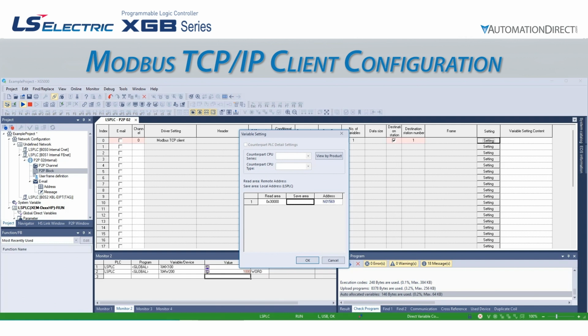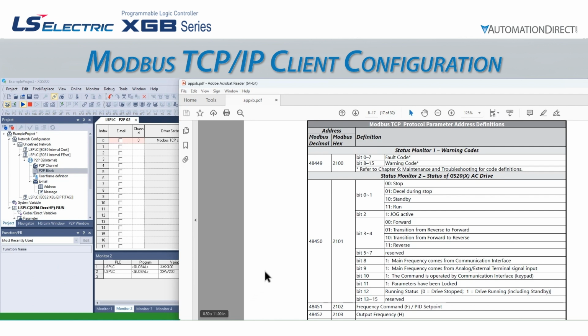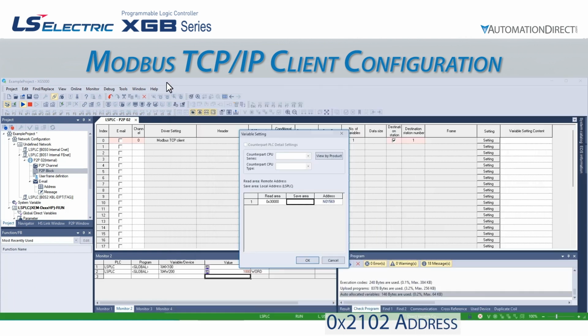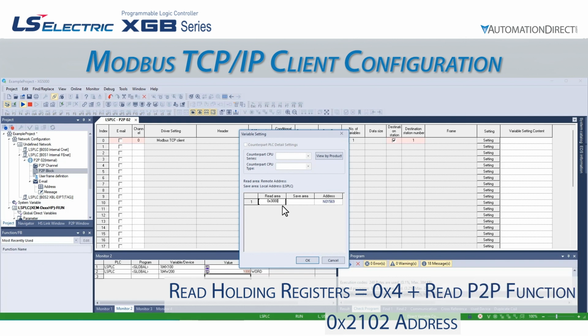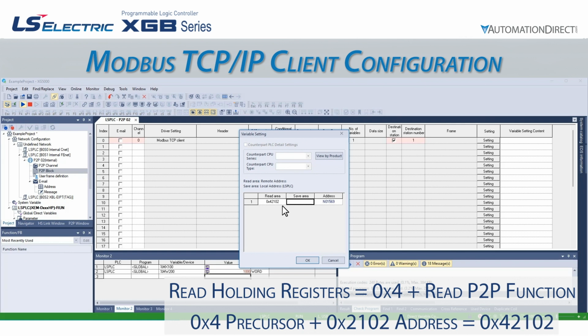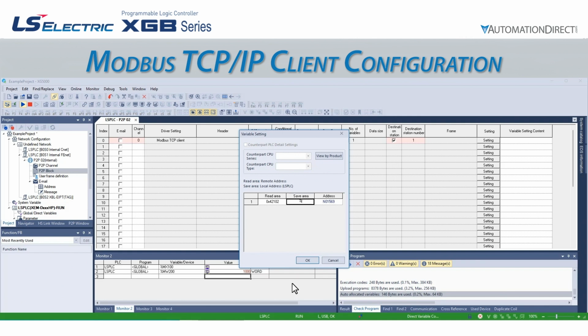For our example, we want to read the commanded speed from the drive. If we look in the drive manual, we see that this resides at hex address 0x2102. In XG5000, we use a 3 or a 4 precursor to select the Modbus function code. In our case, we want to read a holding register, not an input register, so we will use 0x42102. We would use a 0 or a 1 precursor for a bit read or write. We will write this to the internal memory address %MW100.